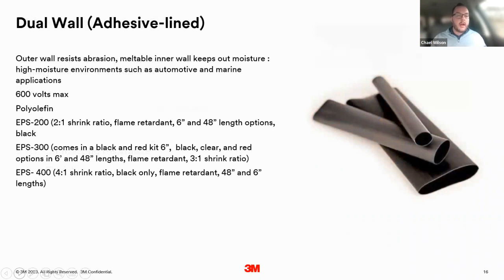We also have dual wall adhesive lined heat shrink. What this does is give you a really good seal specifically for moisture protection, because the inner wall of the heat shrink is actually adhesive, and when you apply heat, it melts and forms to the cable or whatever you're heat shrinking over, and then the outer shell is just your standard heat shrink. So it gives you a really good seal there. It has that 3-to-1 shrink ratio like we talked about before. The only problem is that if you might need to get back into it, it is harder because the adhesive has formed to the cable in that application.